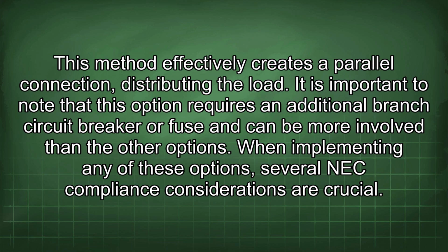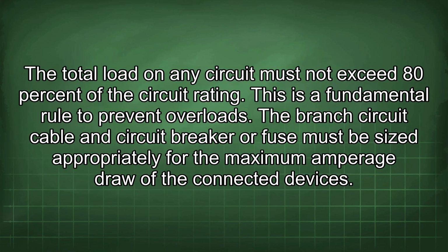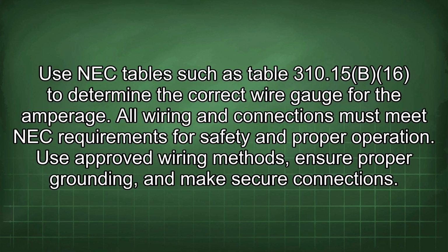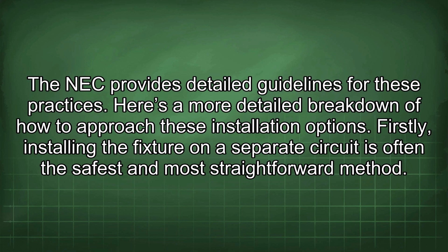When implementing any of these options, several NEC compliance considerations are crucial. A total load on any circuit must not exceed 80% of the circuit rating. This is a fundamental rule to prevent overloads. The branch circuit cable and circuit breaker or fuse must be sized appropriately for the maximum amperage draw of the connected devices. Use NEC tables such as Table 310.15(B)(16) to determine the correct wire gauge for the amperage. All wiring and connections must meet NEC requirements for safety and proper operation. Use approved wiring methods, ensure proper grounding, and make secure connections. The NEC provides detailed guidelines for these practices.